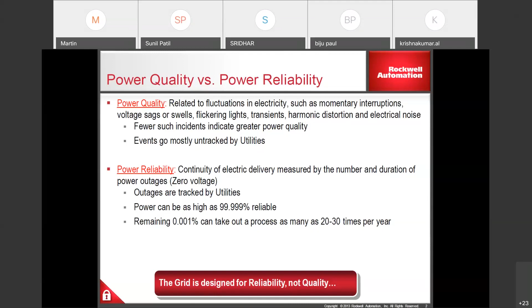Now, what is the importance of power quality? Power quality events are mostly random. They can come from the utility, which includes weather, something like a tree hitting the power line, some accidents, or animals. These are common cases. On the facility side, we know an induction motor starting will demand about 5 times the current, and that can create a voltage sag. And when you have a common transformer shared between different customers, or different sections in a large manufacturing area, that also can give you this kind of problem.